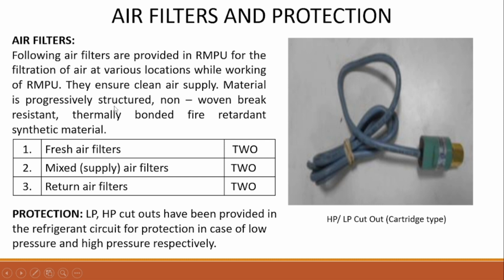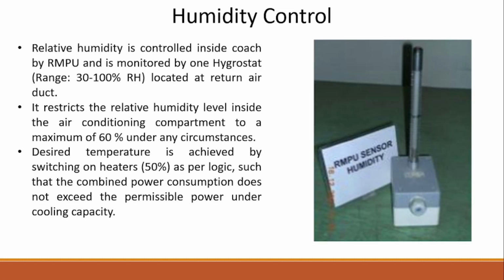The material is progressively structured, non-woven, break resistant, thermally bonded, fire retardant synthetic material, as we can see in the chart. Now, in protection, low pressure and high pressure cutouts have been provided in the refrigerant circuit for protection in case of low pressure and high pressure respectively. In humidity control, relative humidity inside the coach is controlled by the RMPU and is monitored by a hygrostat, with a range of 30 to 100% relative humidity, located at the return air duct.